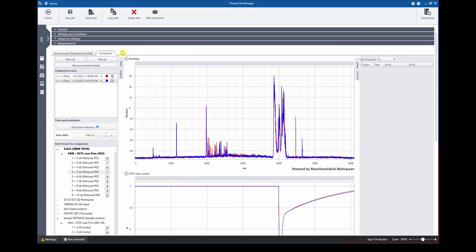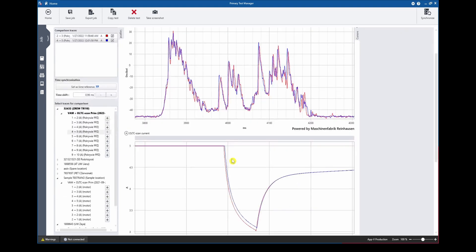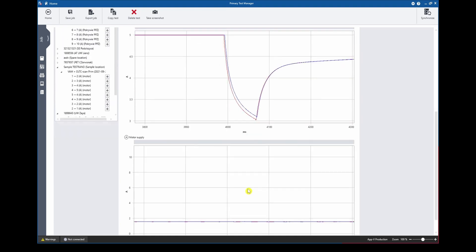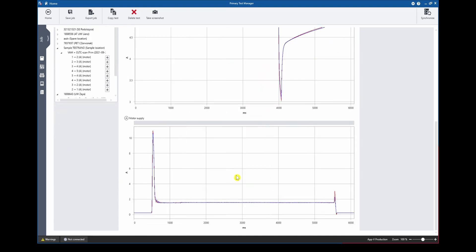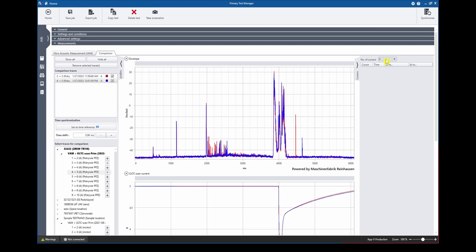Finally, when we are navigating to the comparison tab we can select any curve in our PTM database and use it as reference data for comparison. In this case we can see in red and blue the two envelope curves which are lined up in the top graph and then below we can see as well the dynamic current curve and as well the motor supply current. In addition we can also make use of our cursors and select up to 12 cursors to place them in our graphs and start analyzing the timings.